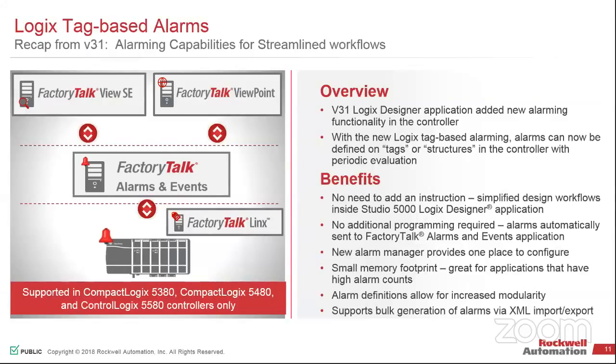You can nest the alarms, so you have the benefit of being able to now put logic around the tags. So if you have, let's say again, a boiler as an example, and a bunch of alarms inside of your boiler, you want to map that up to one boiler alarm. You have the ability now to do that pretty easily with the Logix, or even some code inside of the HMI, without having to do a DB script or anything like that. But your limitation there is 500 milliseconds. Half a second. A half a second.